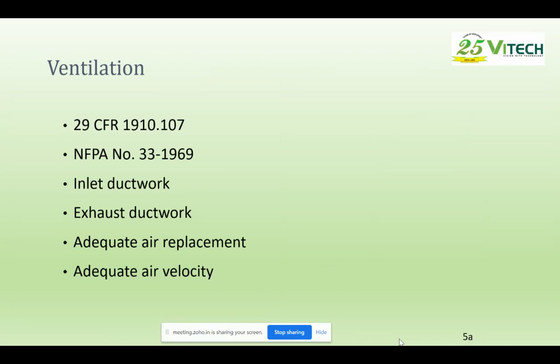The lighting inside the paint booth should be a flame-proof light fitting, and all the motors used are flame-proof motors. Electrical and all ignition sources should be protected. There should be no combustible materials or combustible construction materials. The booth is mainly made of steel sheets. So we follow the standards used in all global practices in the design of a paint booth.